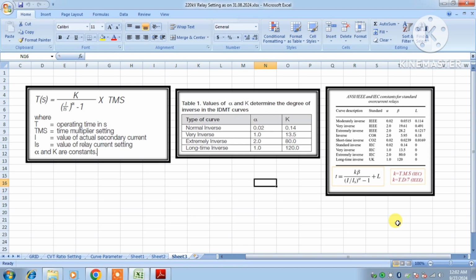If we have the fault current and the setting current, then we can find the operating time, at what time the relay operated during the fault. Knowing that time, we can also verify the settings using this application. So let us go into the application.